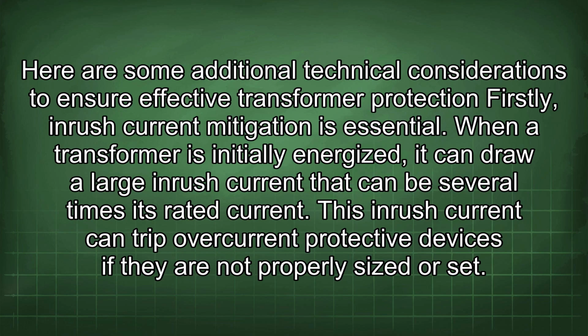Here are some additional technical considerations to ensure effective transformer protection. Firstly, inrush current mitigation is essential. When a transformer is initially energized, it can draw a large inrush current that can be several times its rated current. This inrush current can trip overcurrent protective devices if they are not properly sized or set.